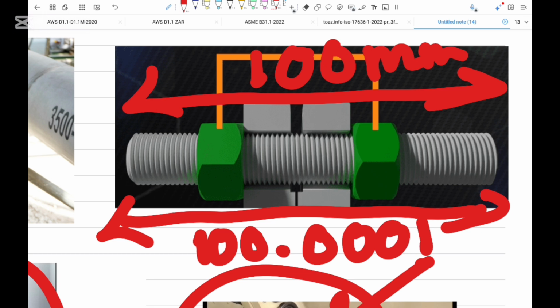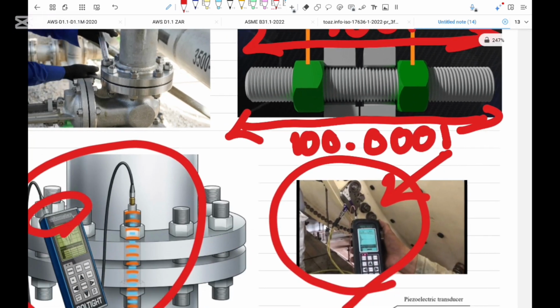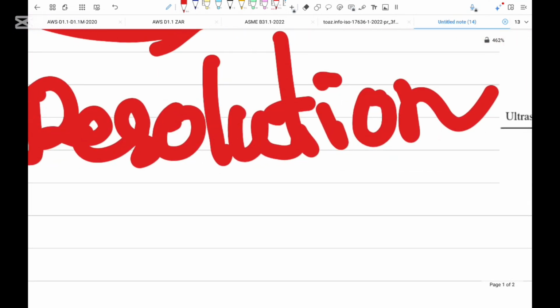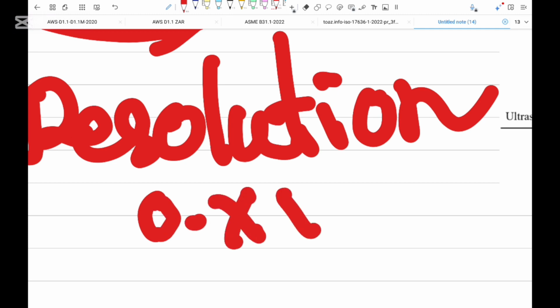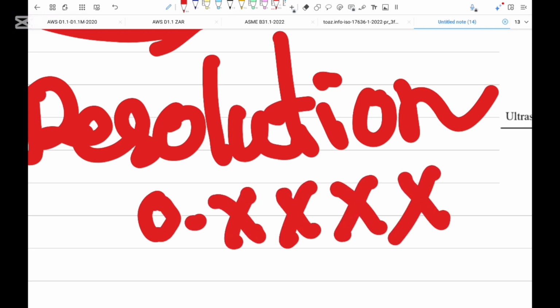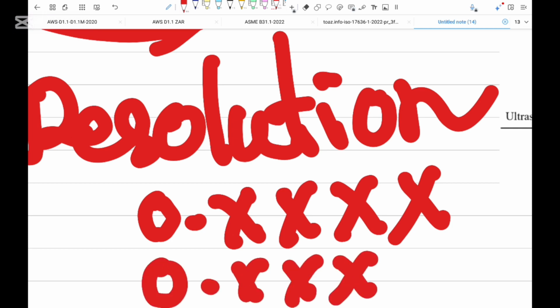Here we need to calculate the tensile stress, right? So we need an accurate data record to calculate the tensile stress. That's why you may require at least 4 decimal digits, but most conventional ultrasonic flaw detectors can only display three decimal digits. That is the one limitation of our conventional UT flaw detector. If your equipment can display four decimal digits, or if your data requires recording only three decimal digits, that is fine, you can use it. That is not a problem.